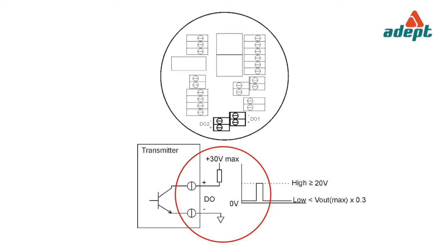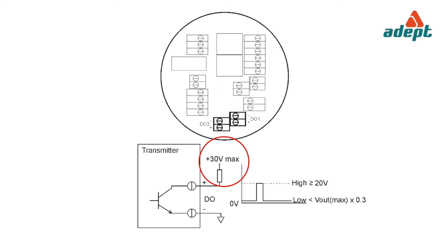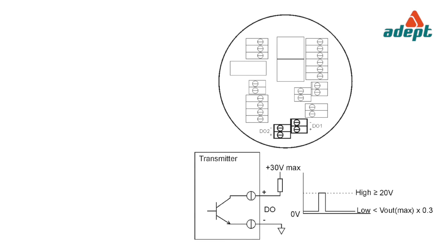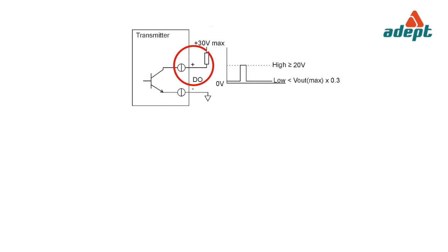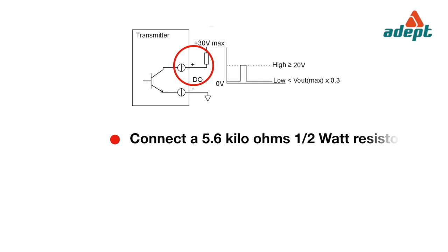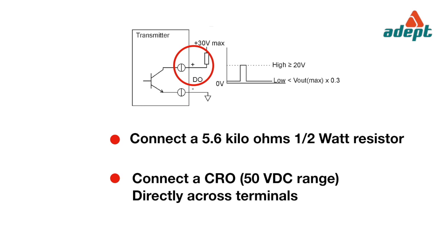Open collector mode: the load is connected between the correct DO positive terminal and the positive of the external DC supply; the negative of the DC supply is connected to the DO negative terminal. The external DC power supply must be within the range of 22.6 to 30V DC, and the load must not be less than 5.6 kilohms. Disconnect the load from the DO positive terminal. Connect a 5.6 kilohm half-watt resistor between DO positive and positive of the supply. Connect a CRO on 50V DC range directly across the terminals.